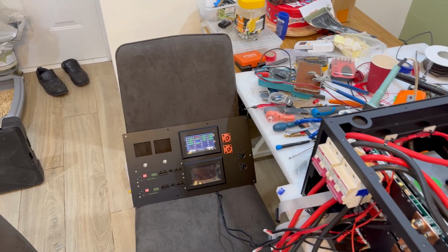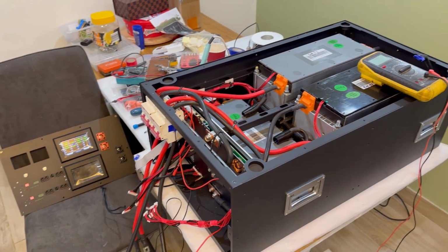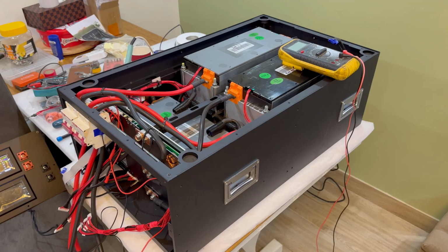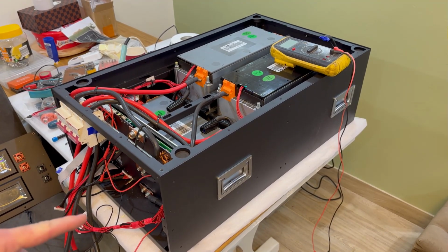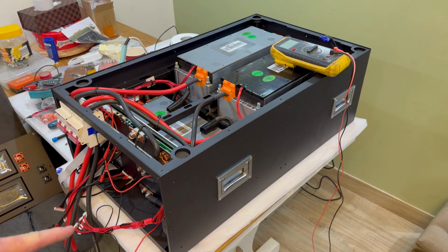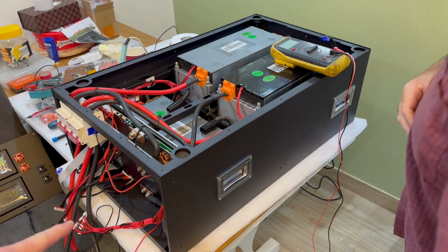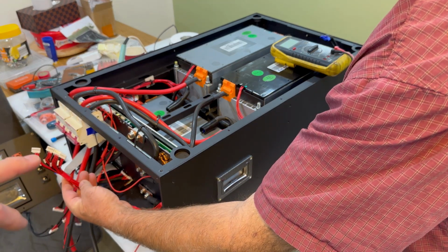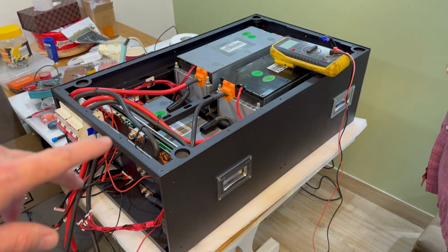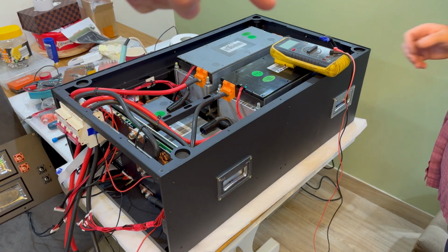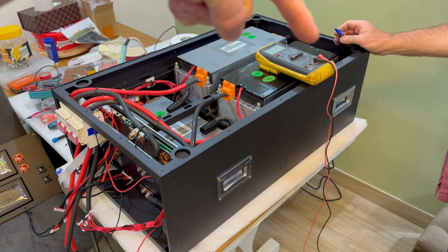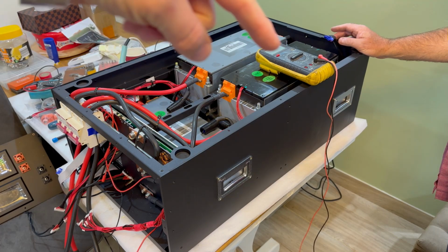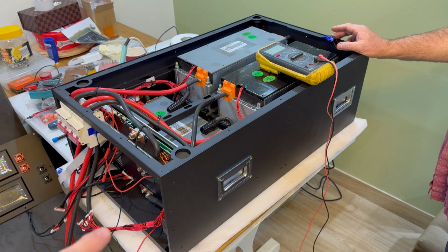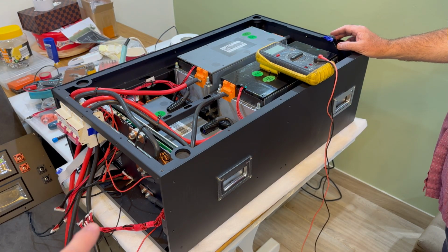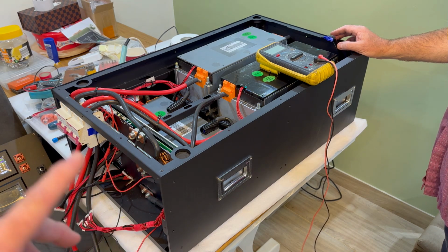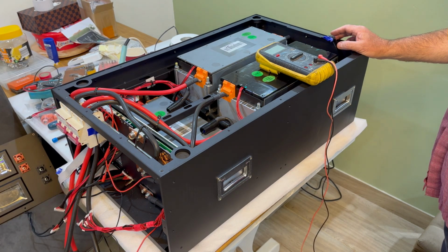What we're going to do now is show you the process for checking your wiring to the BMS on the second battery unit. We've got cables down here, they're all wired in. Before we plug those into the BMS, we're going to take you through the sequence of how we test those. Importantly, the battery cable just behind the meter at the back is disconnected so the circuit is broken and it's totally safe. We'll take you through checking all of that wiring to ensure you've done it right before we plug it all into the BMS.